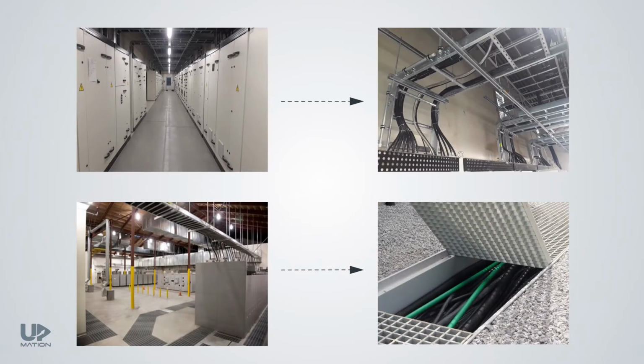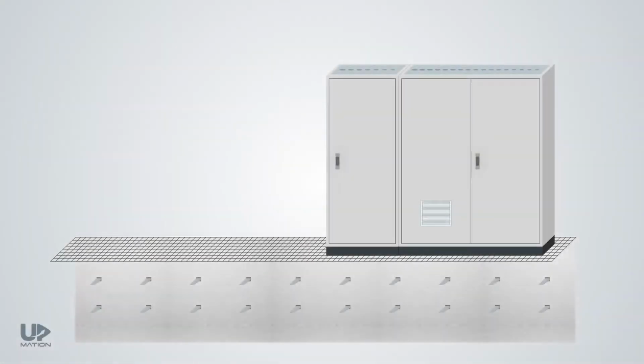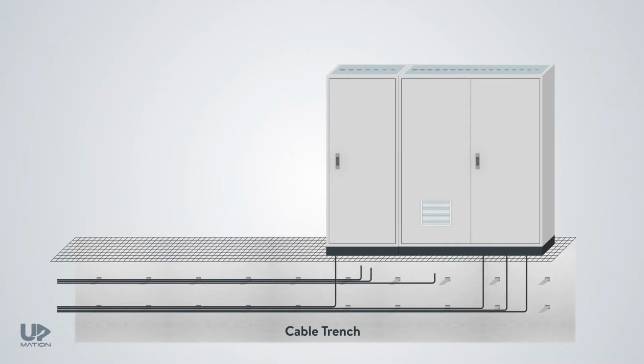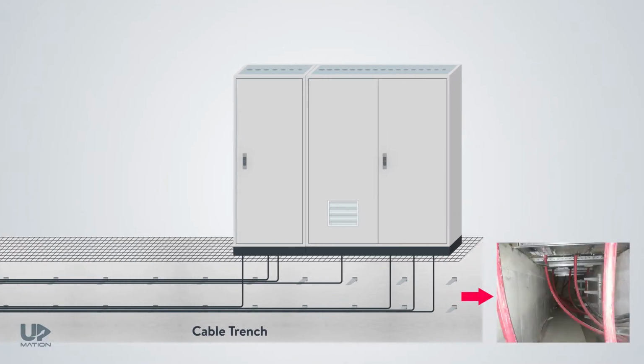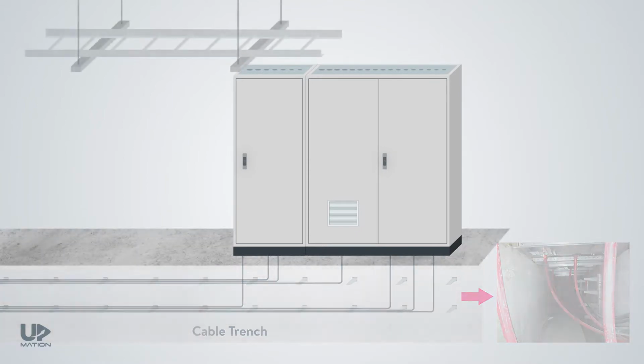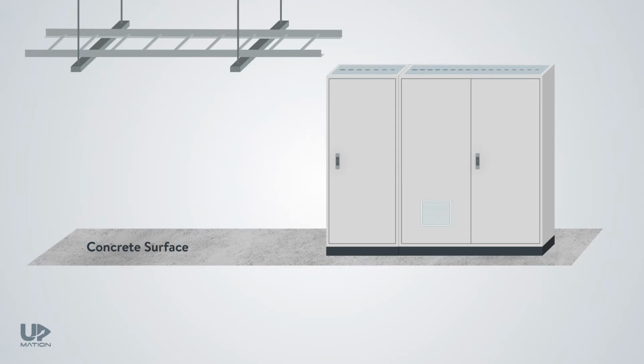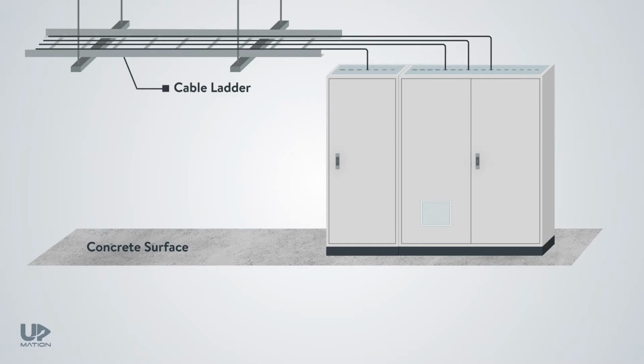You should examine the cable entry of the floor-mounted cabinets in the design phase of the project. Should they be top entry or bottom entry? It actually depends on the architecture of the room. If there are cable trenches, cable tunnels, or raised floors in our project, then we can pull the cables through the floor. In this picture, you see the power cables are entering into the switchgears from the bottom. Yet, if there would be a concrete surface beneath the panels, then there is no way except to choose the top entry enclosures. Pull the cables from the cable trays hanging from the ceiling of the room and bring them inside via the gland plate on the roof of the cabinet.